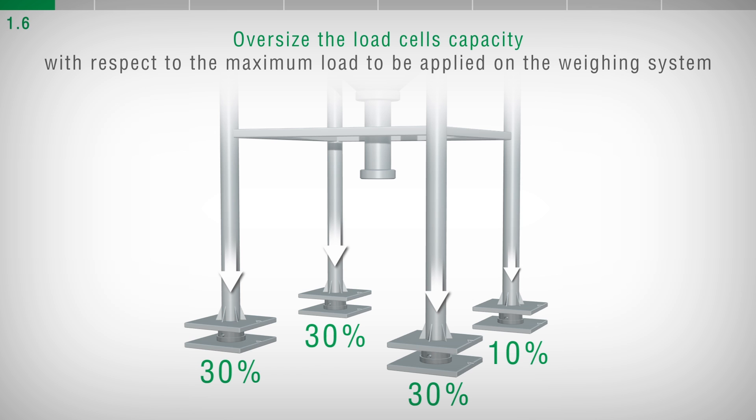consider that the load will not be uniformly distributed and that 85 to 90 percent of the applied load will be distributed on just three supports.